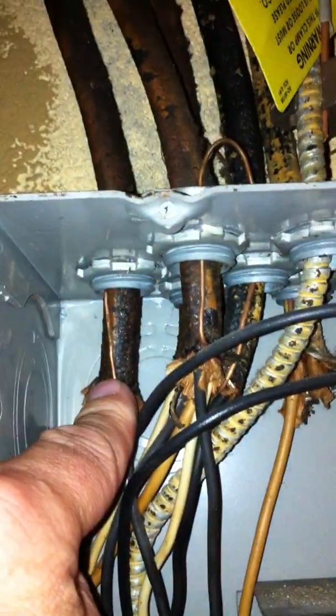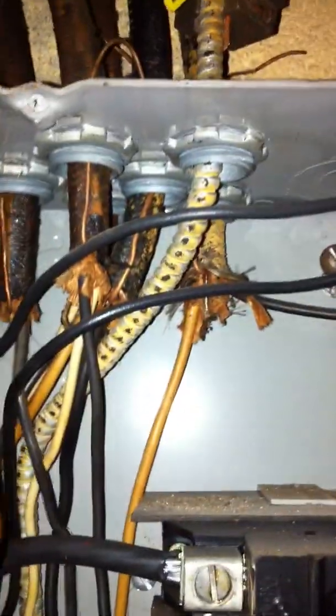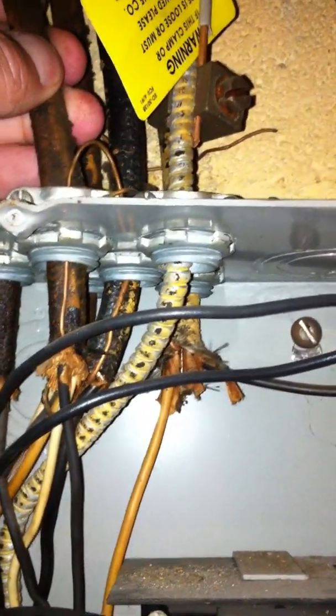Let's take a look where it's coming from. It's coming from this old original — it's 1950s, 1940s cloth Romex. It's got a ground on it. So actually your house is better than having knob and tube. A lot of times old wiring comes in cloth — it's called knob and tube, and it's ungrounded. But you actually have a ground here, so it's actually modern wire — the first bit of modern style wire.